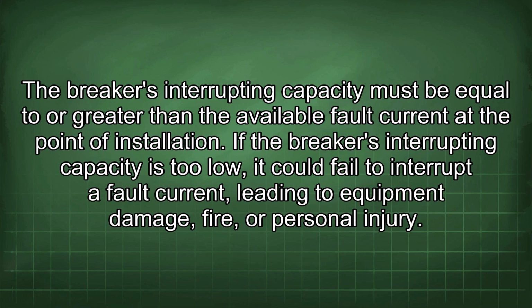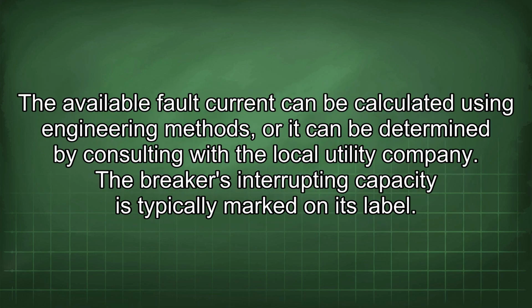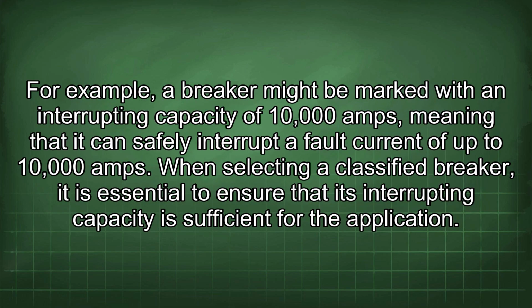fire, or personal injury. The available fault current can be calculated using engineering methods, or it can be determined by consulting with the local utility company. The breaker's interrupting capacity is typically marked on its label. For example, a breaker might be marked with an interrupting capacity of 10,000 amps, meaning that it can safely interrupt a fault current of up to 10,000 amps. When selecting a classified breaker, it is essential to ensure that its interrupting capacity is sufficient for the application.